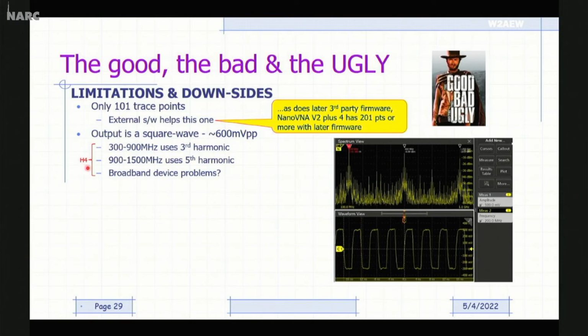So in the case of the H4, though, it uses the fact that a square wave has energy at odd harmonics to actually make measurements. When you're making measurements up to 300 megahertz, it's using the fundamental frequency. This is showing the square wave output, and this is the spectral content of it. So there's energy at the fundamental, energy at the third harmonic, energy at the fifth harmonic. The H and the H4 will use the energy at the fundamental to measure the responses. But when you get above 300 meg up to 900 meg, it's actually using the energy in the third harmonic. And from 900 to 1500 megahertz it's using the fifth harmonic.